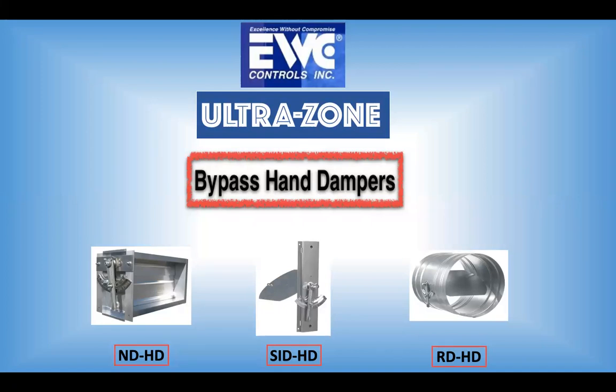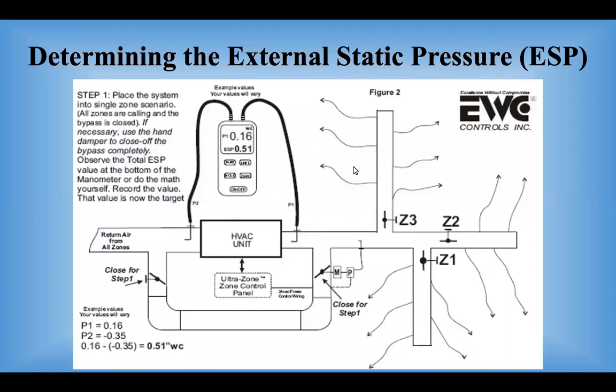And why do we do that? Well, a bypass is another supply duct. We've balanced the rest of the system. This is the first one off. This has to be balanced as well. If we don't balance that, the air takes the path of least resistance, which will be this bypass duct, and it will race around there, stealing velocity and airflow to our zones, and also at the other end, supplying so much return air that we don't pull proper return air from the structure. So we need to install this balancing damper and or hand damper before it re-enters the return air.